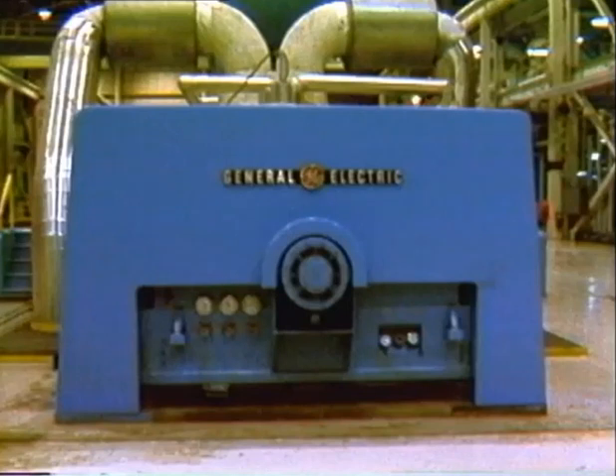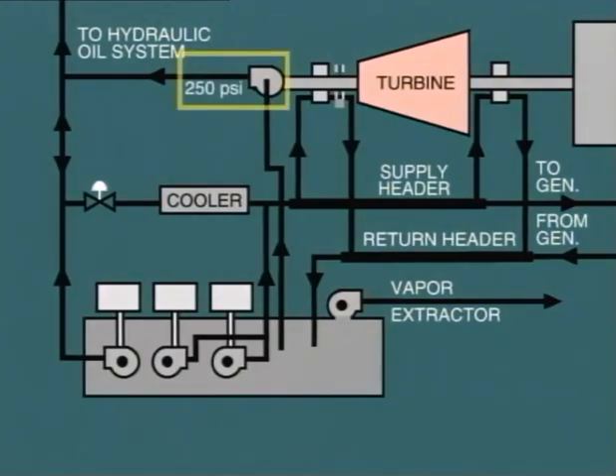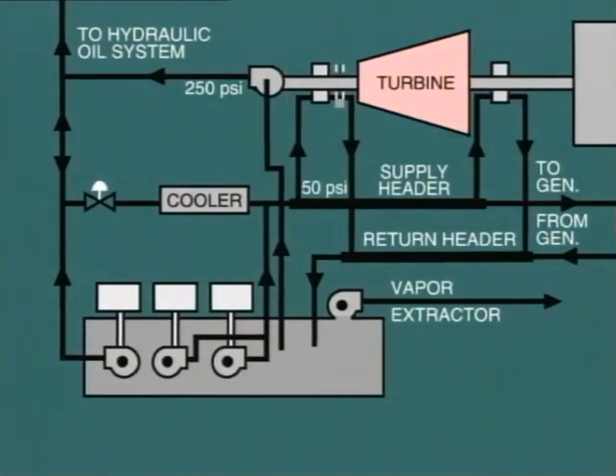The main oil pump is mounted in the front end pedestal and is driven directly from the turbine shaft. When the machine is in operation, the main oil pump delivers oil at 250 PSI, supplying the hydraulic oil system. At the same time, it provides oil to the lube oil header at 50 PSI through a reducing valve.